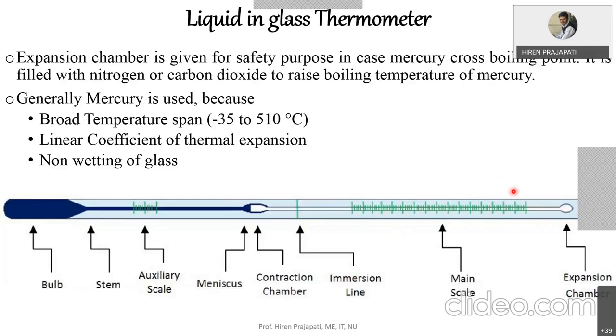The expansion chamber is used for safety purposes and is filled with nitrogen and carbon dioxide, which raises the boiling temperature of mercury if mercury is the filling liquid. Mercury is commonly used because of its advantages: a broad temperature span from -35°C to 510°C, a linear coefficient of thermal expansion over the entire temperature range, and non-wetting of glass.